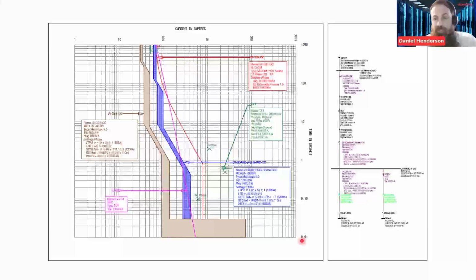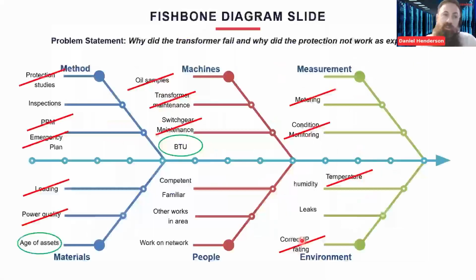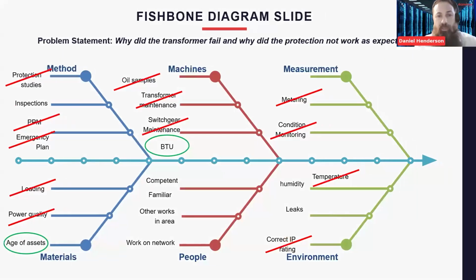Coordination. Again, just a snapshot, but we had the protection coordination study done. That was in place, and we'd had the trip time testing done on the switchgear as part of the maintenance. Again, that was individual, so it was one at a time. We haven't verified the whole board, so maybe there are some areas that need to be verified, but I'm fairly happy that those settings are in place.